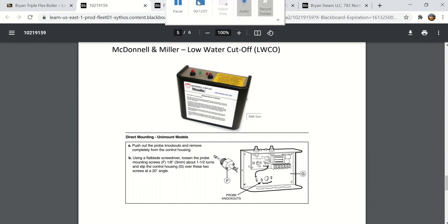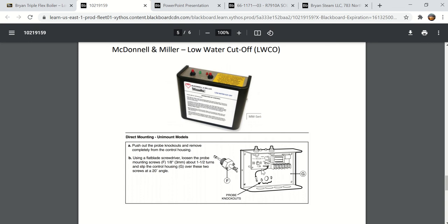One thing real quick, I think I got a little bit of time left. On the low water cutoff here, one common problem with these electronic low water cutoffs is that the circuit board is attached to the metal casing with these standoffs and screws, and these screws actually do ground the board to the standoff there. If that circuit board or these screws come loose, it does not get a good ground reference, and that will cause nuisance problems with these. So that's something to always look at. If you take the cover of a low water cutoff like this off, make sure that the board is securely attached to these standoffs, because if it's shaking loose, that will give you some nuisance problems.